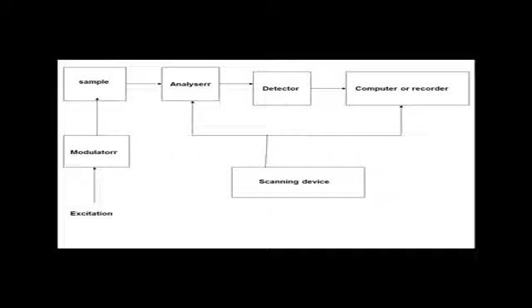Coming to emission instruments, schematically a typical spectrometer, the excitation can be thermal or electrical, but usually takes the form of electromagnetic radiation. In the latter case, it is essential that the detector does not collect the radiation directly from the exciting beam, and the two are placed at right angles as shown in figure. A modulator fixed between the source and the sample together with a tuned detector amplifier ensures that the only emission recorded from the sample arises directly from excitation, neglecting other emission.